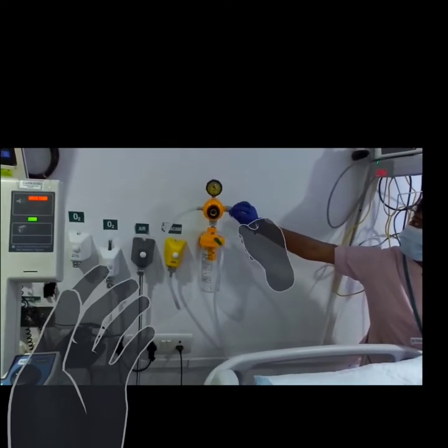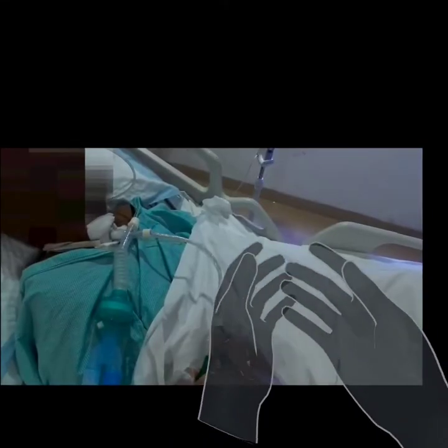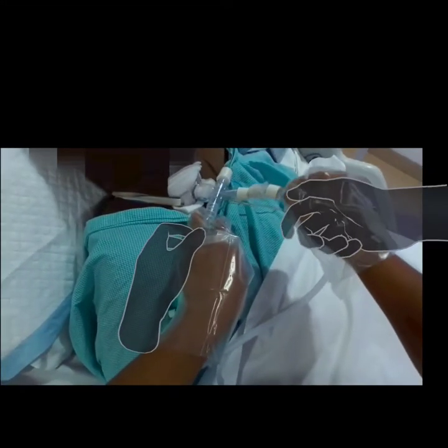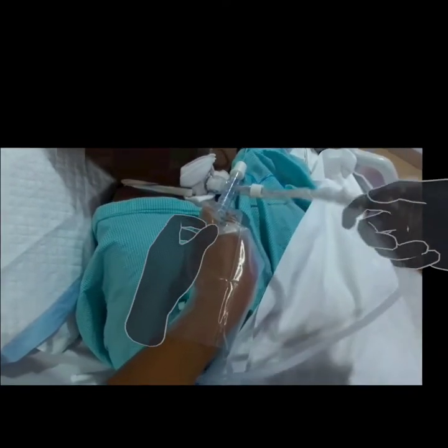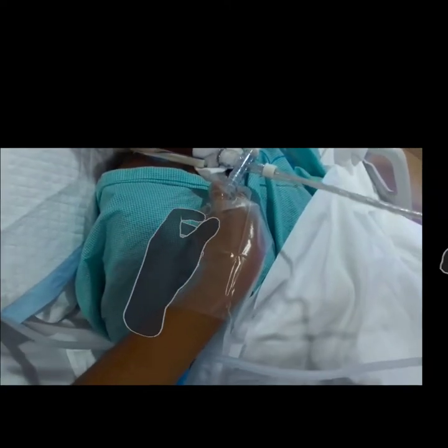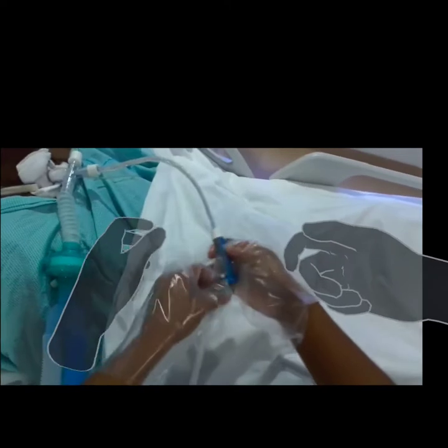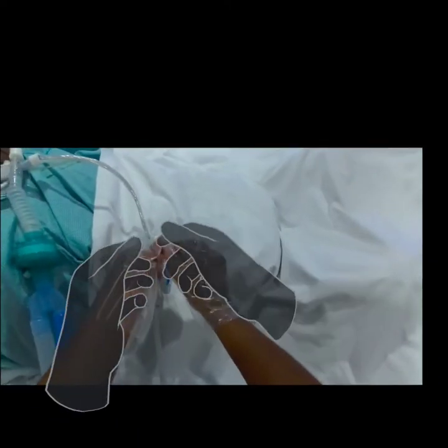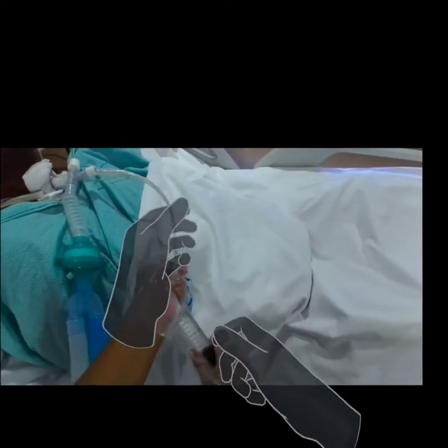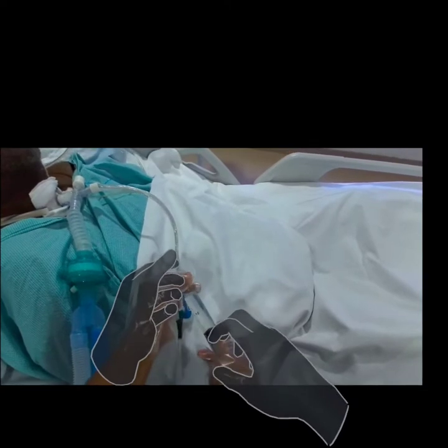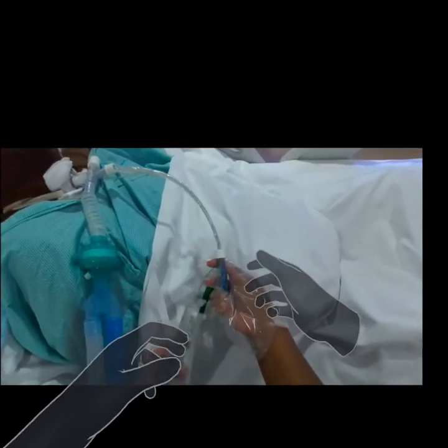Switch on the suction knob. Connect the Yankauer one end to the patient suction port, the closed suction port. After connecting it, insert the closed suction catheter into the trachea. Once it has reached the trachea, you have to pull out by pressing the blue knob down. You have to keep the suction catheter inside the trachea for 10 seconds and withdraw it. After withdrawing, you have to flush the suction catheter through the flush port with 20 ml of saline.